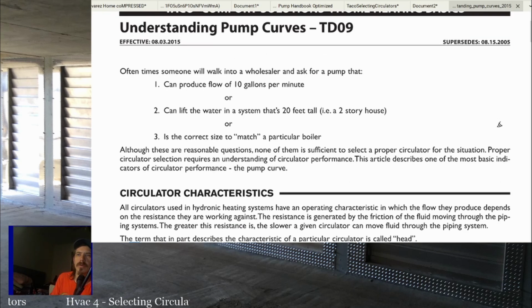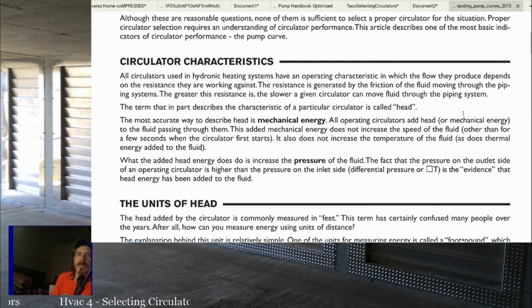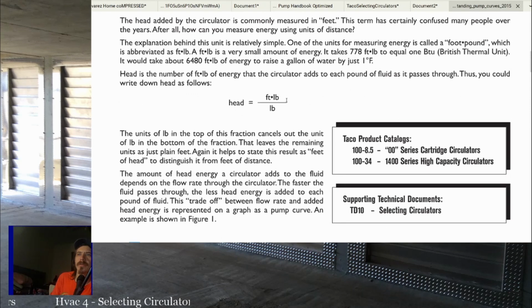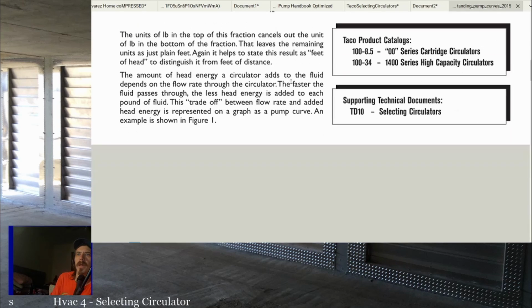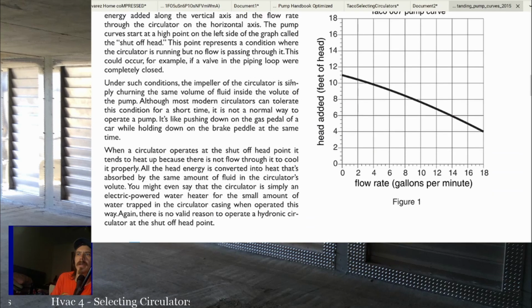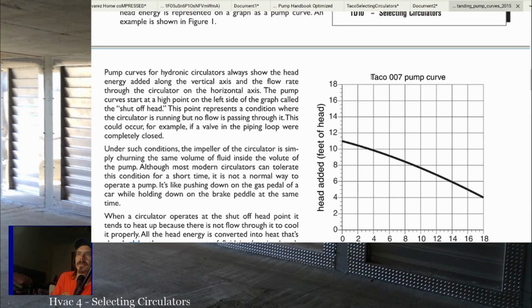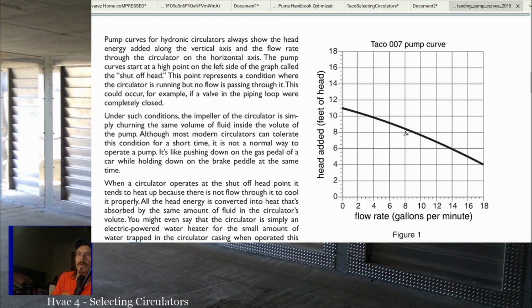Selecting a circulator requires an understanding of the circulator performance, and this describes one of the most basic indicators, the pump curve. So I'm not going to read through this whole thing, but I will go down, and this is a pump curve, right? So this is just another pump curve. So remember, we were looking at the 007 pump curve on that other chart, but this is the actual pump curve for just the 007.